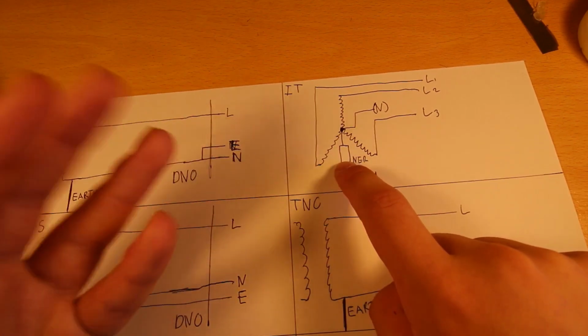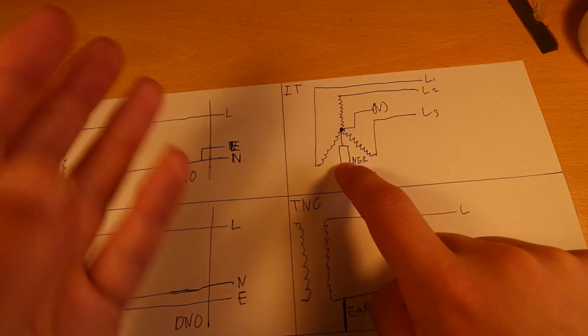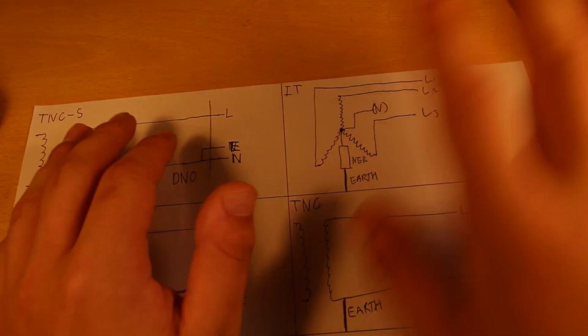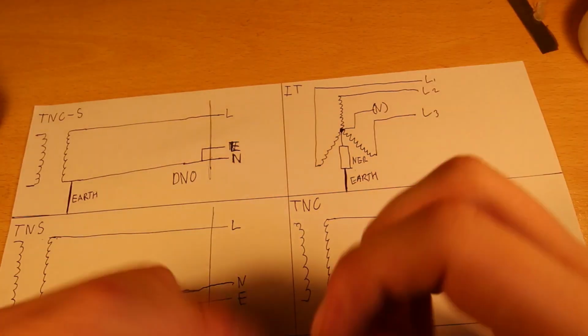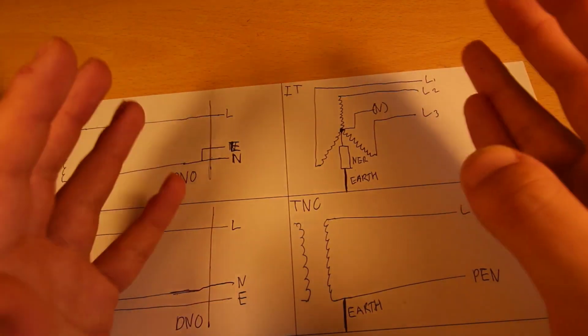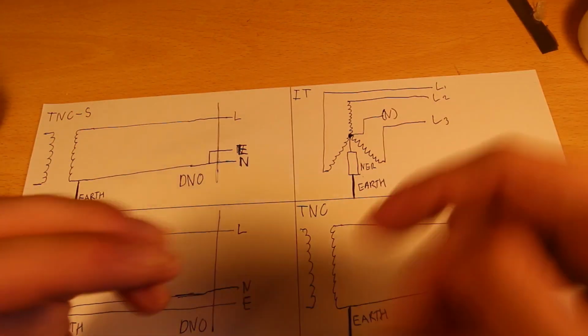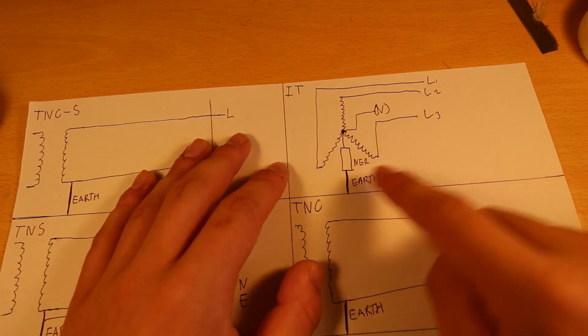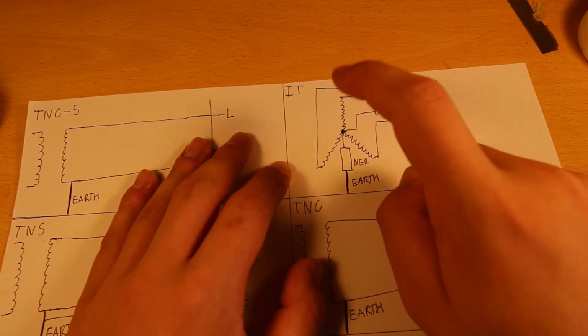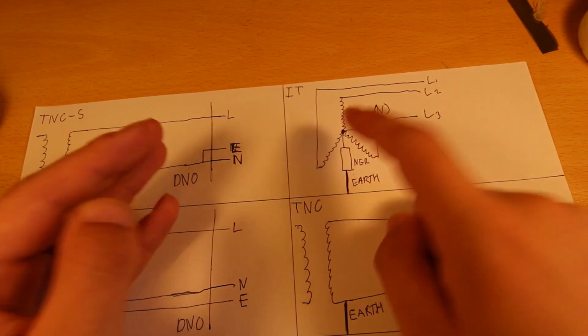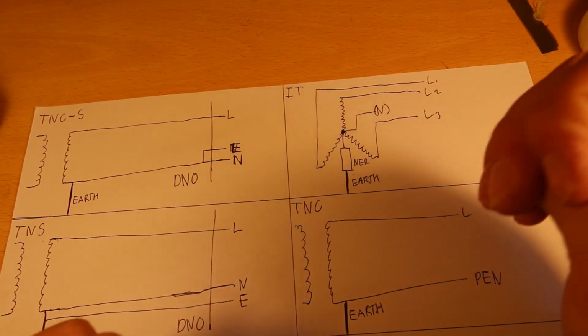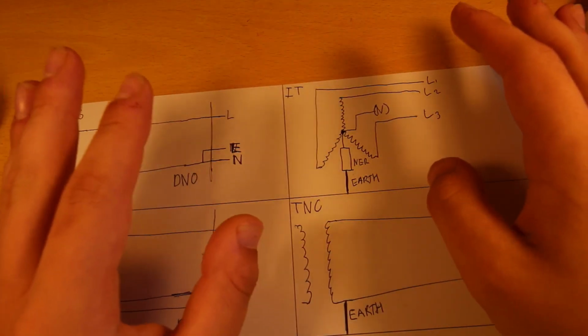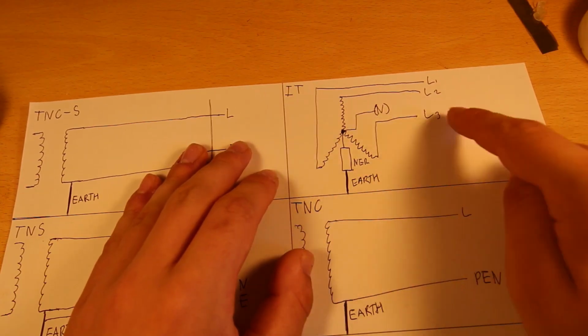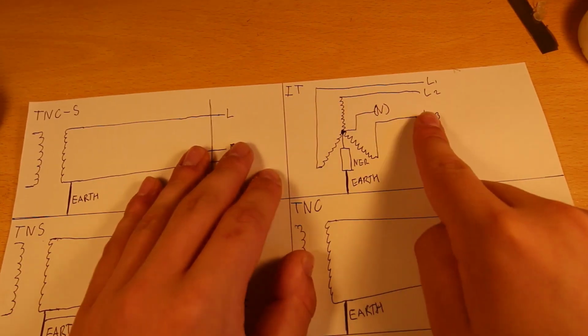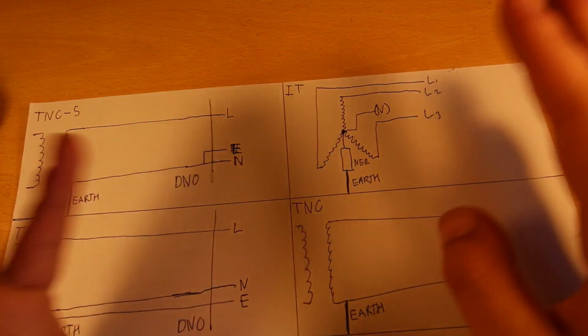So on all high voltage transmission lines in the UK, ranging from 11 kV right up to 400 kV, as I understand it, are current limited to a maximum earth fault current of 1000 amps by the neutral earthing resistor. You would take a neutral from that point too if you wanted to use it, but they don't have neutrals on the high voltage for UK stuff. But that's why it's in brackets.